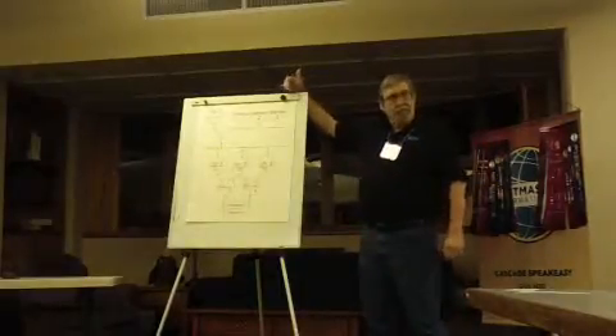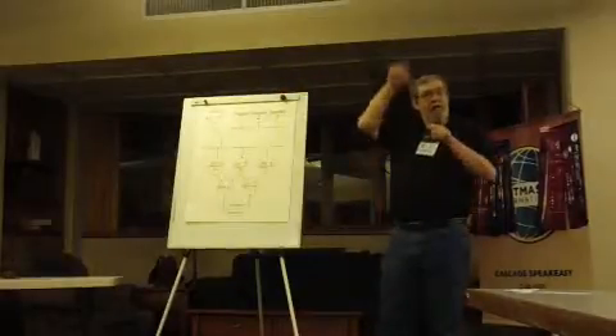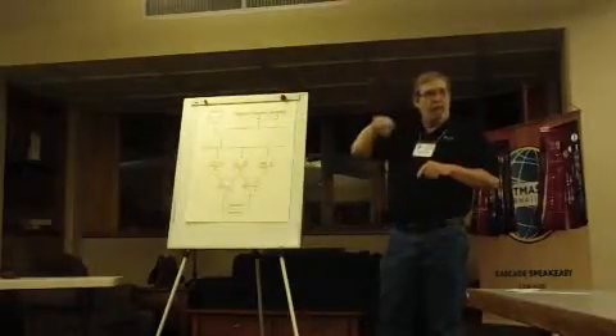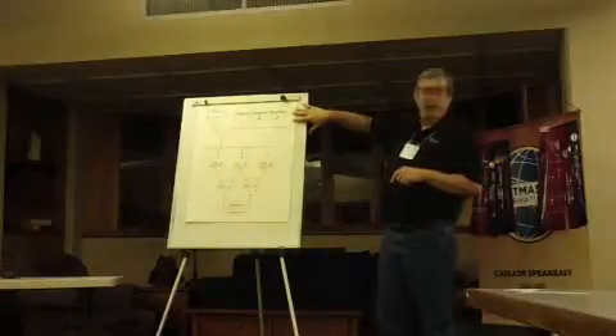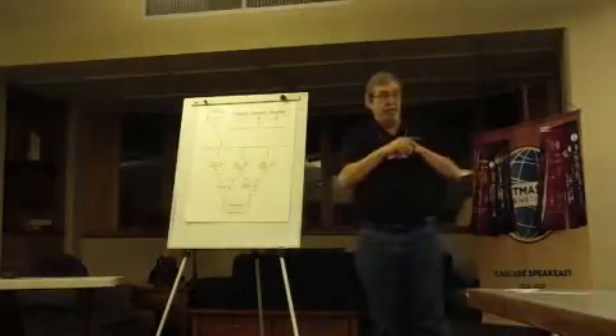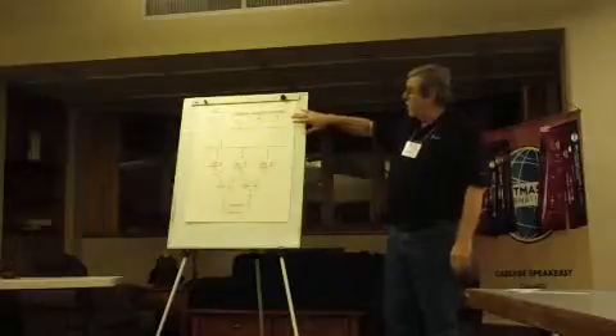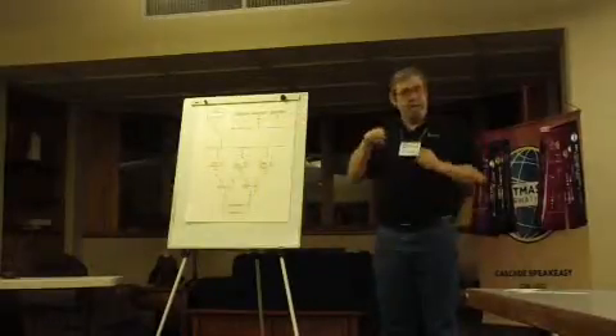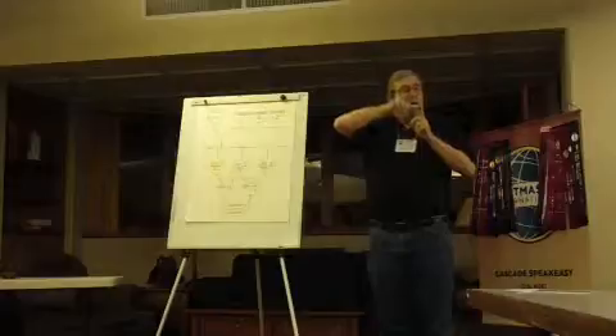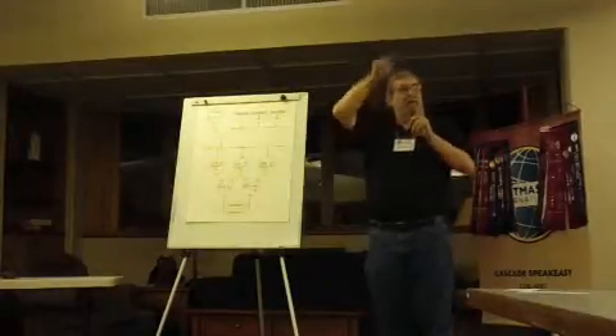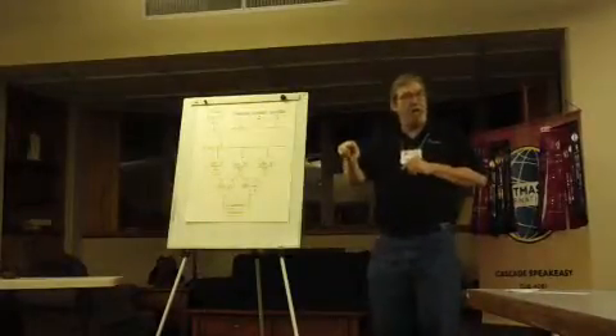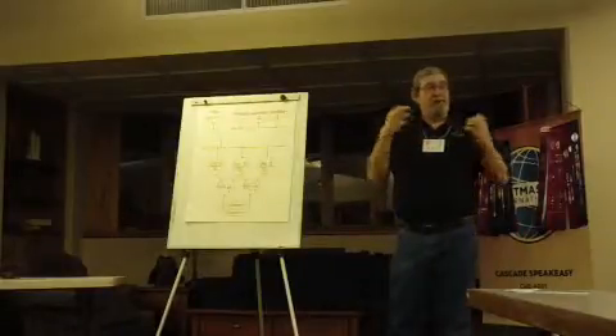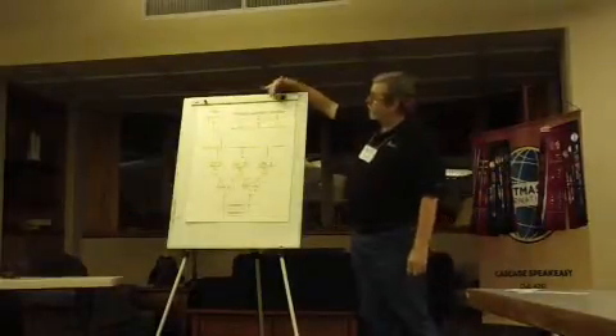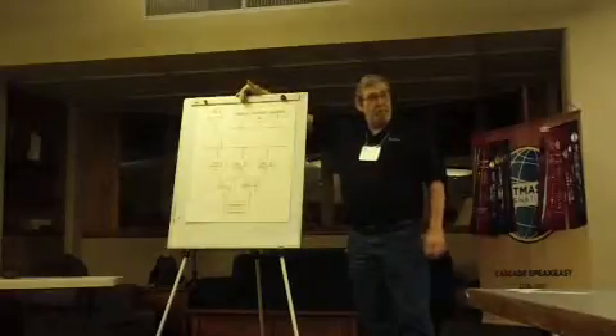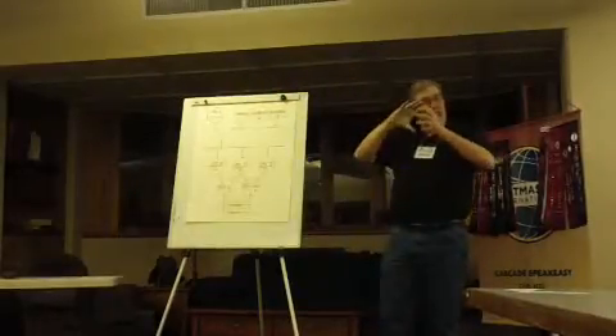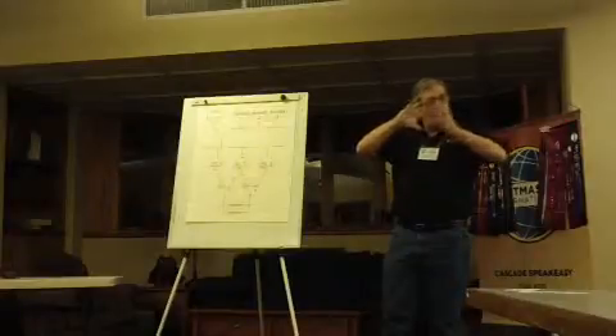Now, the interesting thing about alternating current is you have a positive and negative electricity, and we're dealing at my data center with 13.2 thousand volts. So these have to sync. As a positive wave cycle goes up, all the generators have to be positive at the same time, and they all have to be negative at the same time. So there's a sync check relay that makes sure that as these fire up - they fire up at different intervals but run at slightly different speeds - they all catch up with each other and sync together.